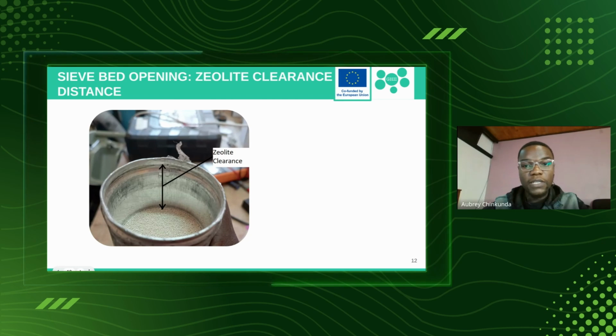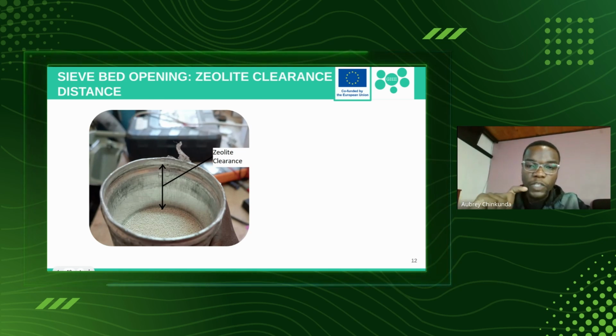Once you open the sievebed, you'll see the zeolite doesn't reach the end of the sievebed; there's some clearance kept. As mentioned, there's usually a filter after the sievebed, a filter disc, and then a spring on top. That clearance accommodates the spring, even compressed, there's always some space remaining. You need to take note of this clearance, measure or mark it, so that when refilling you maintain the same clearance and avoid overfilling or over-compressing the sievebed, which can cause issues like overheating.